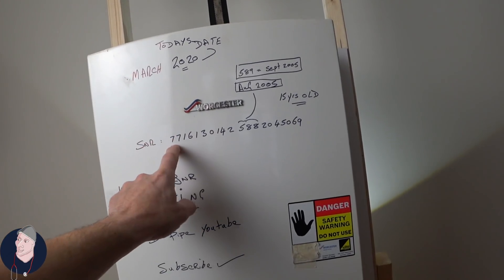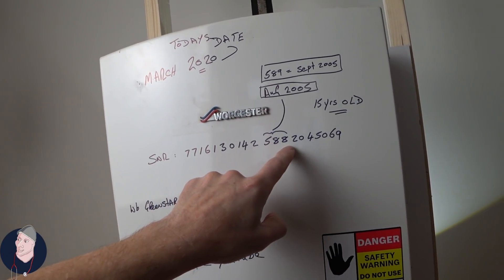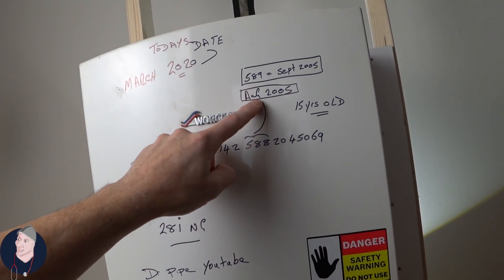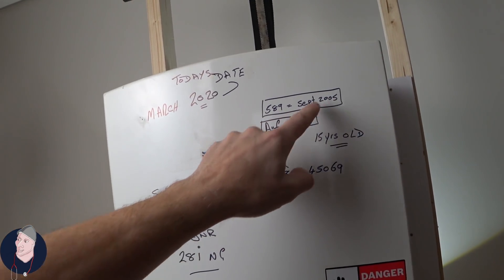Let's go to work. Worcester Bosch — what do we know about this? Serial number: 588 signifies August. Worcesters have got their own codes for these, so 588 is August. If you add 589 it'd be September 2005.